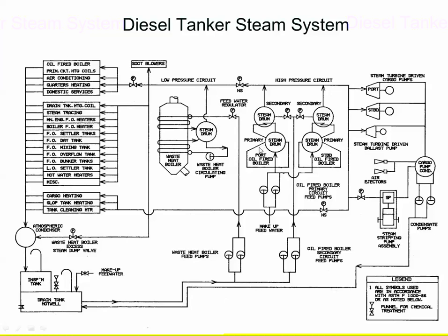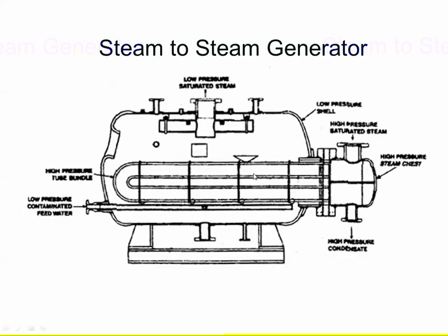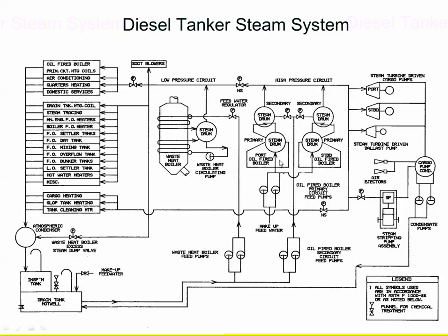And it's going to what they're calling a steam-to-steam generator. Think of your contaminated vat on the steam system, on the Haven, right? You've got a dry pipe here. This is full of water. I have the steam coming in, transferring heat into that water to boil it. As it changes state and goes into a liquid, then it flows back to the drum again. So I can have Drew come in, initially set up the chemistry on this boiler, and that's my whole cycle right there. So I have a closed feed system. I absolutely have a closed feed system, and I didn't have to put in any expensive DA heater or anything else.